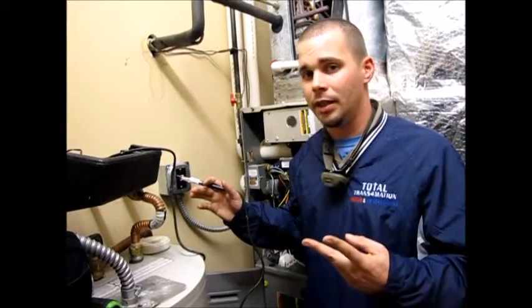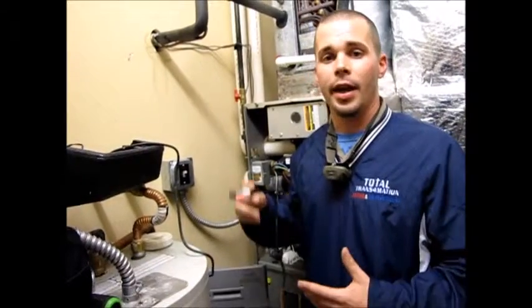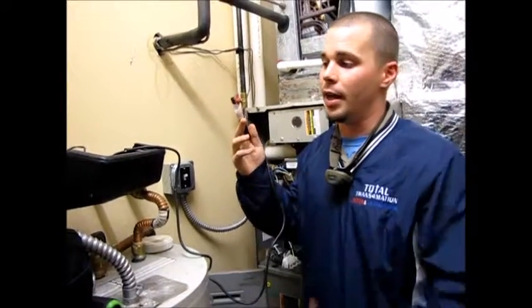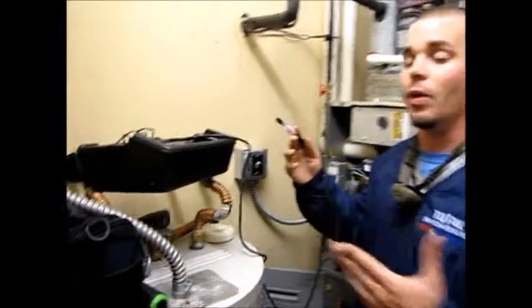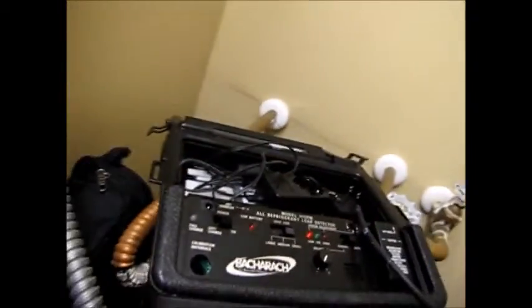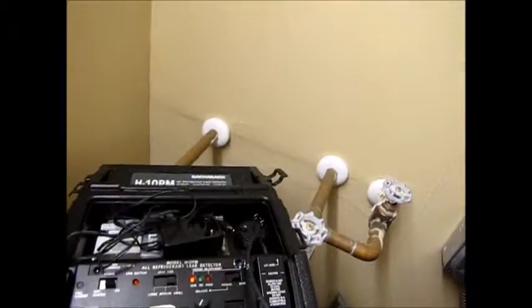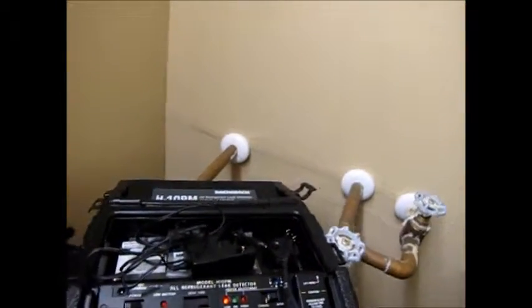The second option is you need to have a leak search performed. What I'm holding here and what we're using today is an electronic leak tester. This is an industry standard for being one of the best. It will pick up leaks within a matter of seconds, depending on where we can locate it and what's going on.